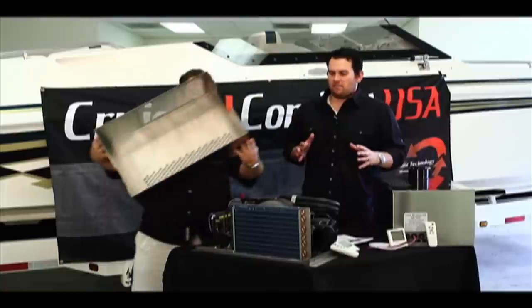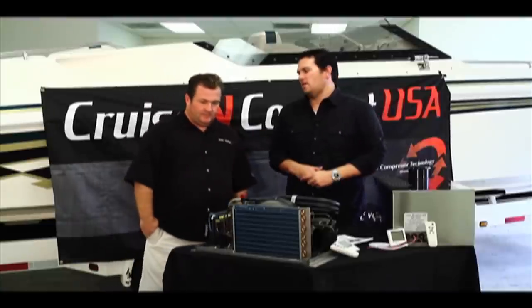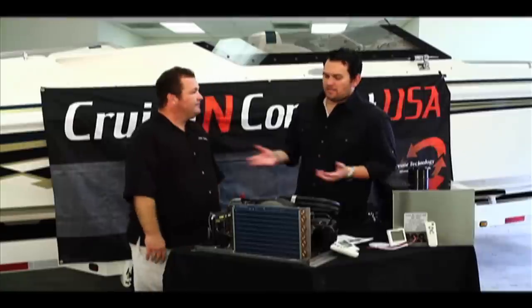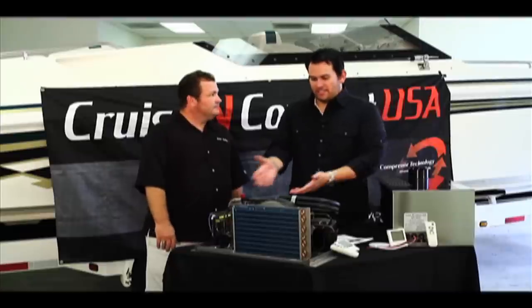Let's get to the nitty-gritty of it and take off the case here to show what we're working with. You talk about the stainless steel caging, but then you have your proprietary technology inside this unit. Breaking down the internals: 300 CFM blower, two compressors, fluid heat exchanger. We have R-134A style service ports that allow anybody to service the unit. That's another accolade to the Cruise N Comfort product — easy serviceability and durability. It's tunable and easy to access; take that cover off and it's right there.